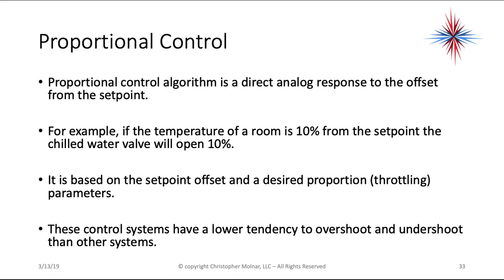Proportional control is an algorithm that is a direct analog response to the offset from the set point. For example, if the temperature of a room is 10 degrees from the set point, the chilled water valve will open 10%. It's based on the set point offset and the desired proportion, also called throttling parameters. These control systems have a lower tendency to overshoot and undershoot than other systems because of the direct proportional response.